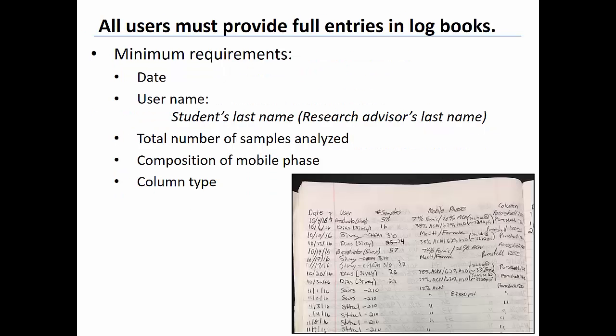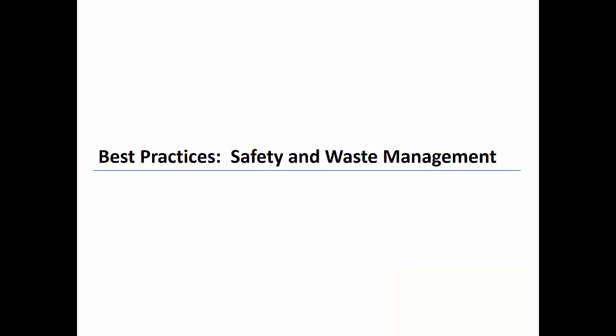Use of logbooks is essential for the proper documentation and upkeep of all analytical instruments including HPLCs. Prior to each analysis, HPLC users must enter, at a minimum, the date, username, research advisor's name, number of samples analyzed, composition of mobile phase, and column type into the logbook.